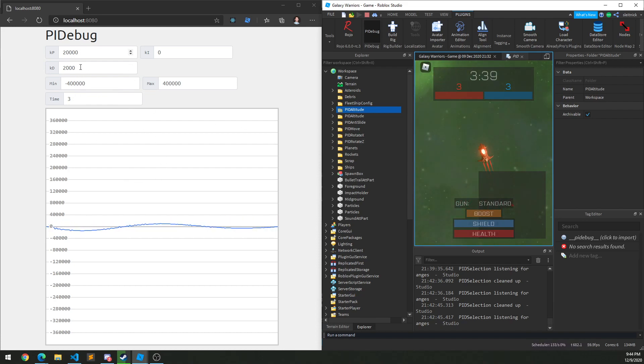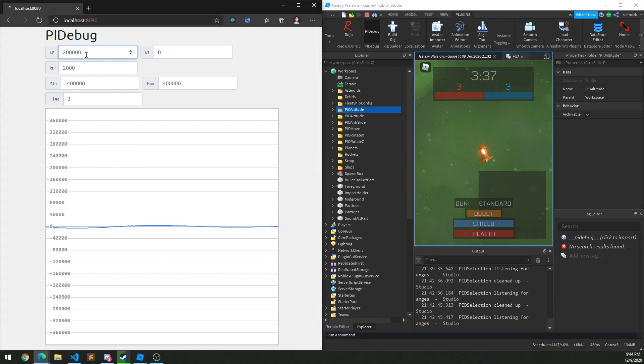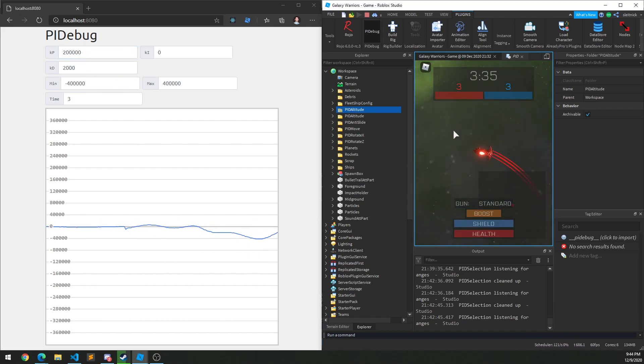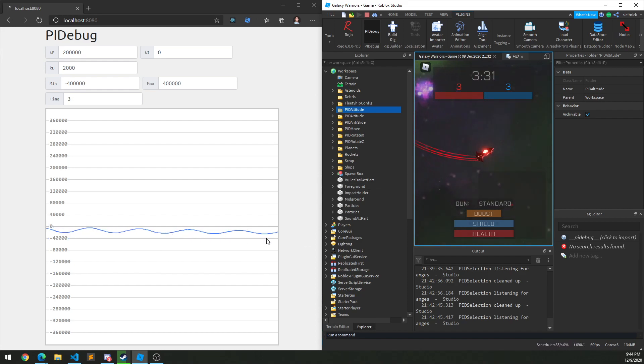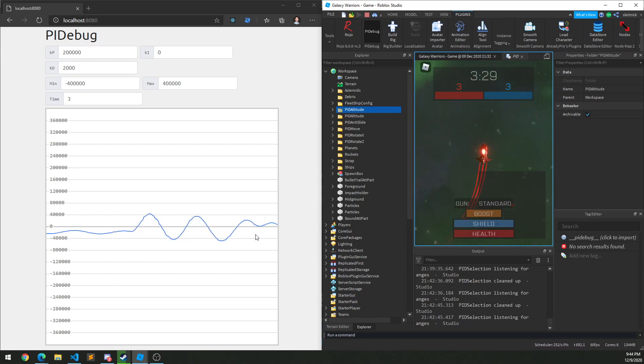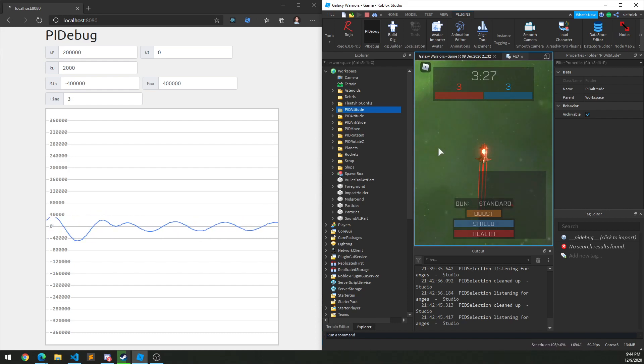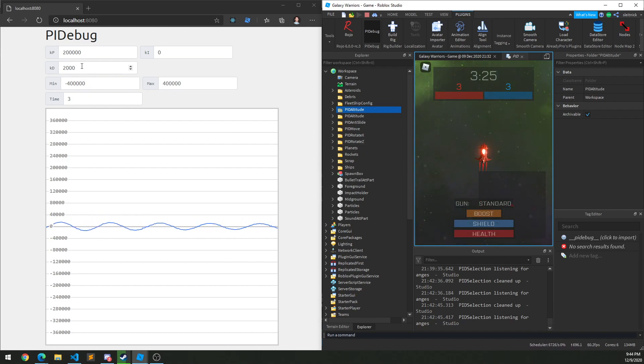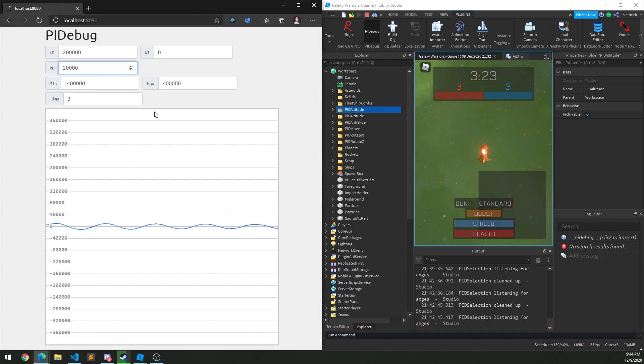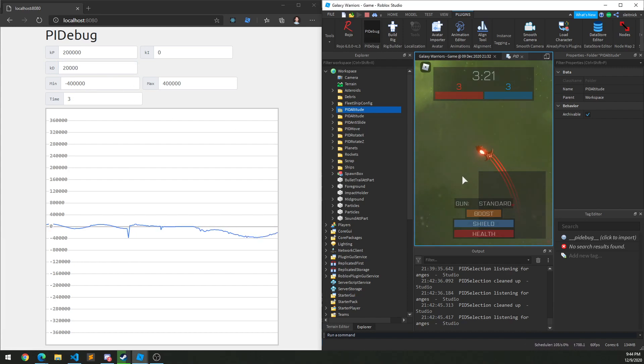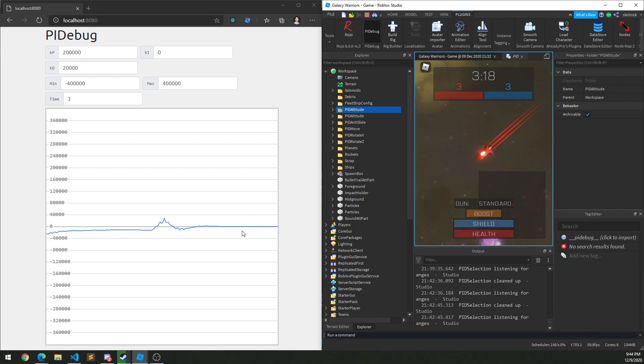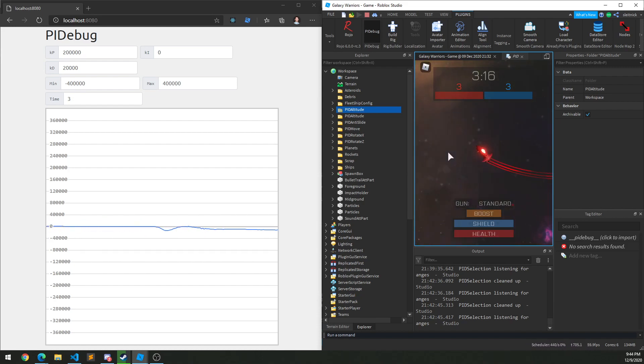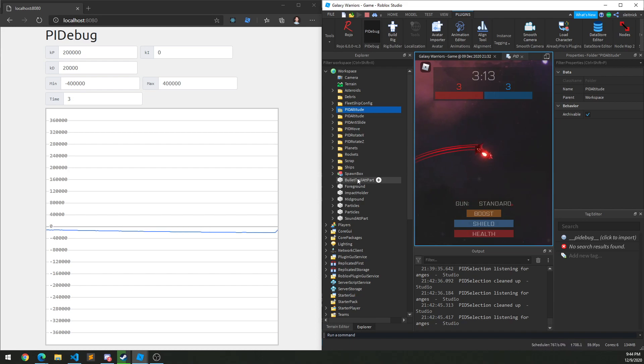So it's not perfect there. Maybe I'd want to change that a little more. Maybe I'd want to make my max P there a little higher. It helps a little bit, but you can still see it's kind of waving back and forth. You want to avoid the waves. That's an oscillation effect that's common in PIDs that you're trying to get rid of. So maybe I'd increase this even more there. And there we go. Now it seems to have gotten rid of that kind of bounce in the wave there from the graph.